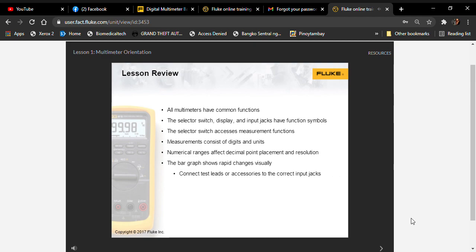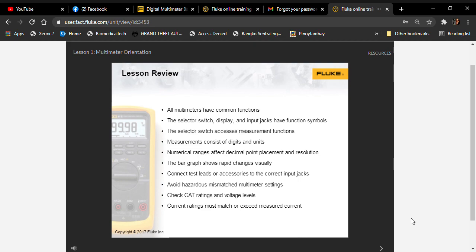The black test lead is connected to the black common input. However, the red test lead is connected to different inputs, depending on the measurement. Some combinations of function selection and jack connections can be hazardous if the test leads contact energized conductors. The multimeter must have CAT and voltage ratings equal to or higher than what is required for a measurement task. When you measure current, the input jack ratings must be equal to or higher than the current you're expecting.